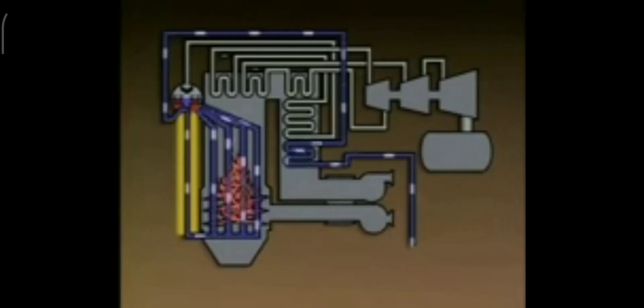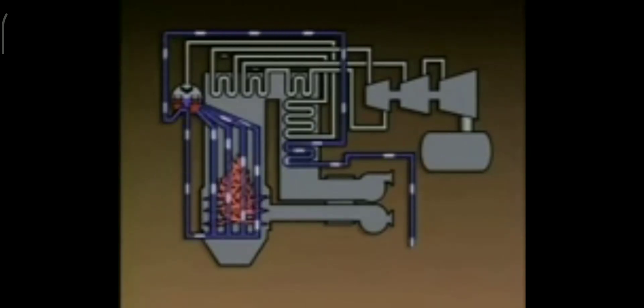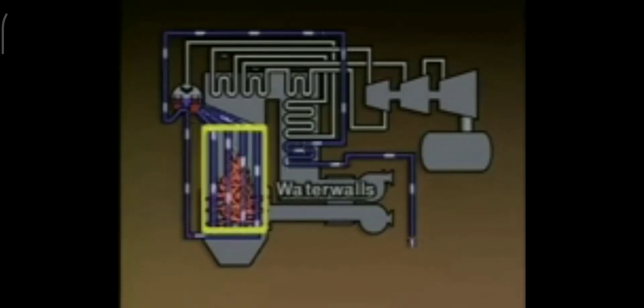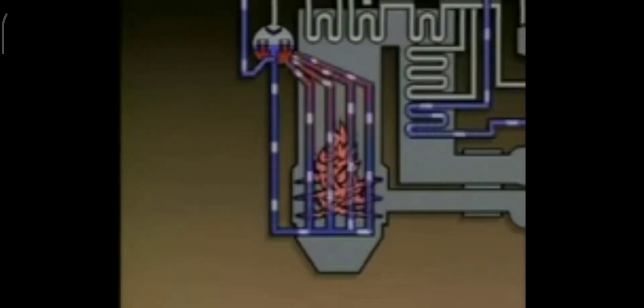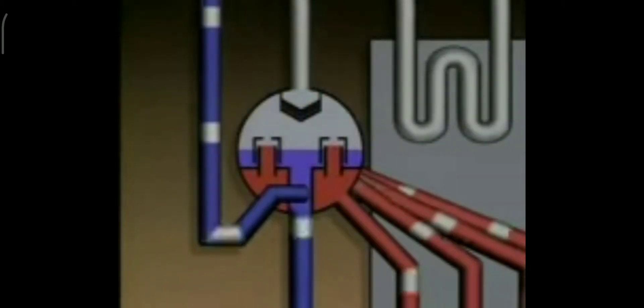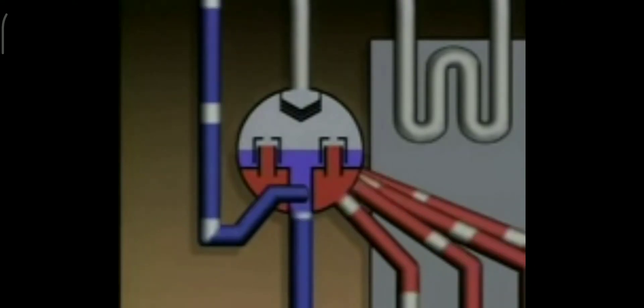A boiler typically has two or more downcomers and two or more headers; however, for clarity, this illustration shows only one of each. The lower headers supply water to the bottoms of the boiler tubes. The boiler tubes, which line the inside walls of the boiler furnace, are commonly called water walls. The water walls are exposed to the heat produced by burning fuel. As water flows up through the water walls, heat turns some of the water into steam. The mixture of water and steam rises until it enters the boiler drum, where it is separated into water and steam. The steam rises to the top of the drum, and the water remains in the bottom. The water is then available to recirculate through the boiler.